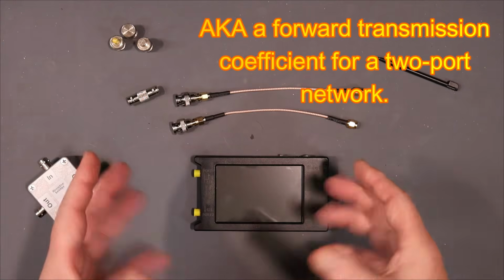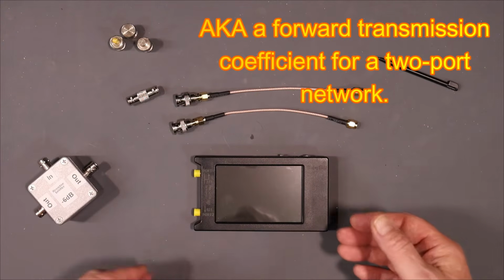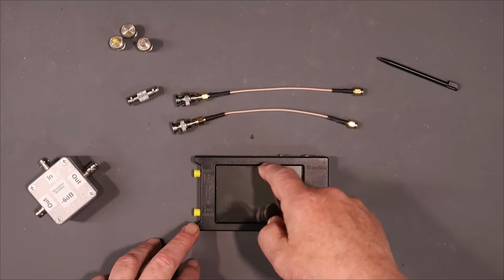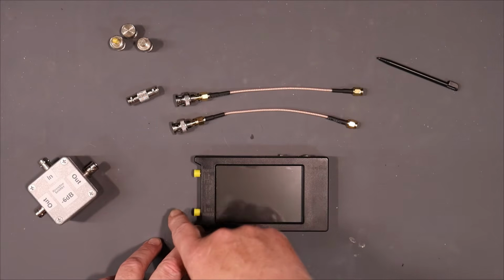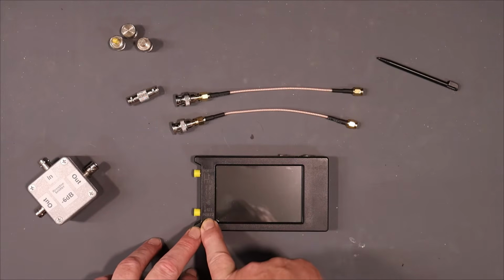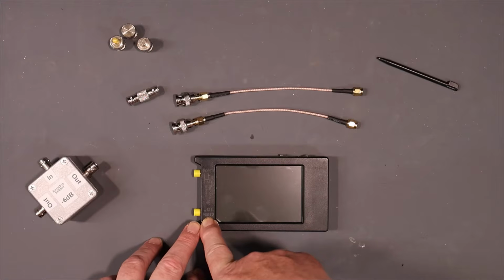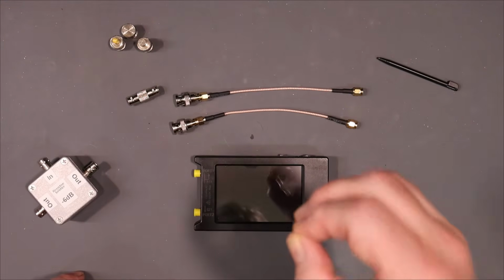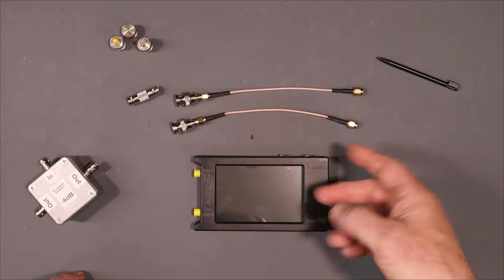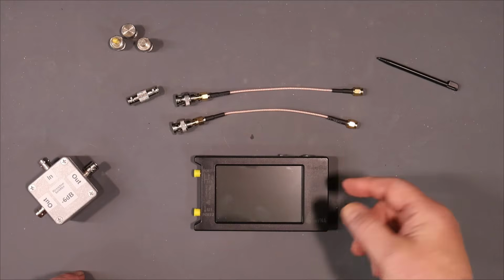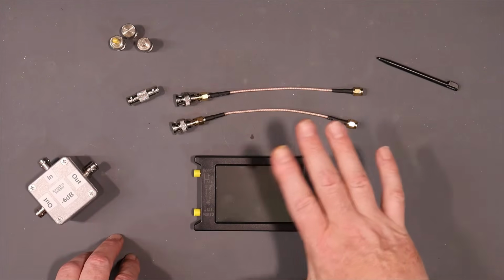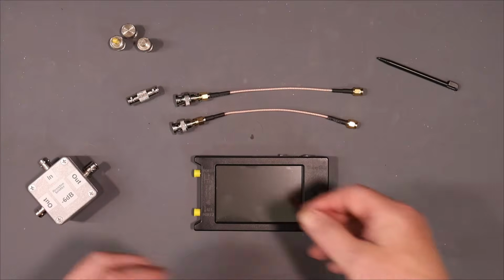I'm not really a VNA expert, but what I believe that means is that it's going to have an excitation coming out here out of port 1. And coming into port 2, it's going to read the results of going through. We've got to do an open calibration, a short, a load, an isolation calibration, and then a through calibration. Before we even get to that point, we need to set up some other parameters.